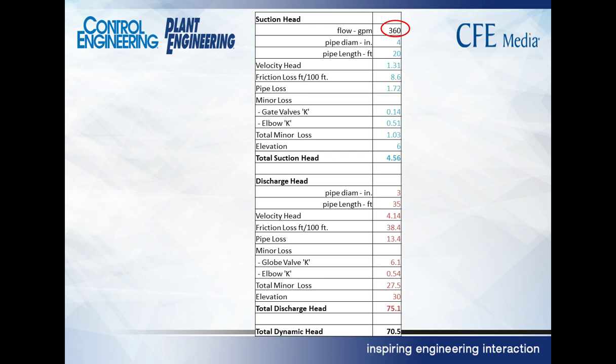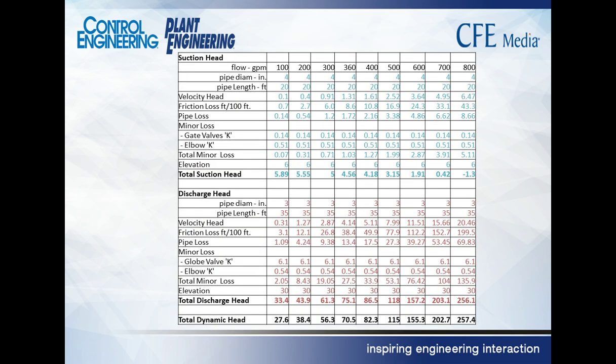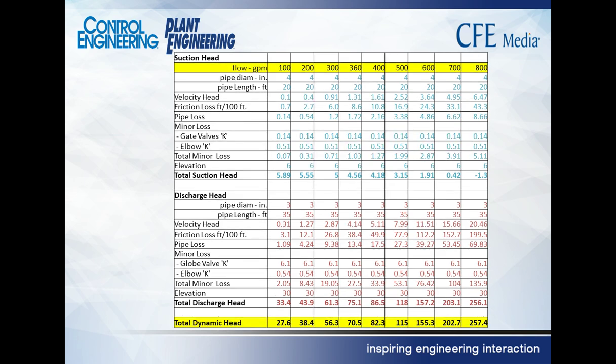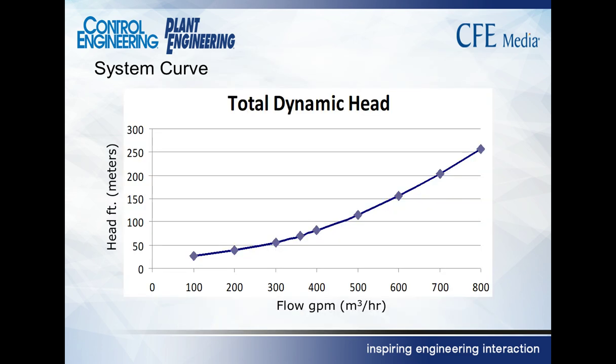Why don't I take that column, since it's a spreadsheet, and copy and paste it about 6 or 7 times? Now I've got a spreadsheet that shows me the total dynamic head at the bottom of the column for any flow rate entered at the top, and I've conveniently entered 100, 200, up to 800. Now let's highlight that top row and the bottom row. Click that little icon on your spreadsheet that says, I want to see this in a graphic format, and you have a system curve.